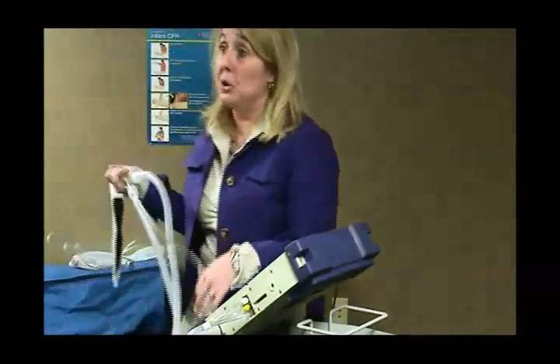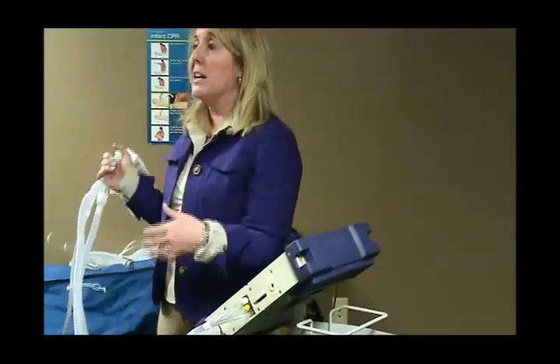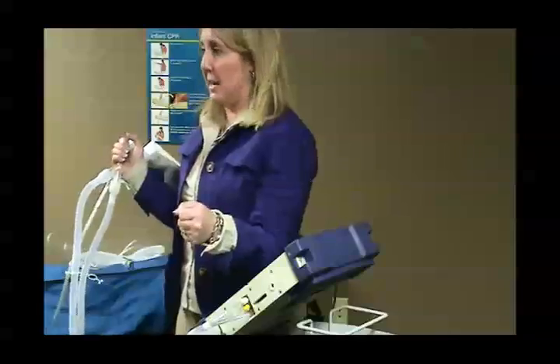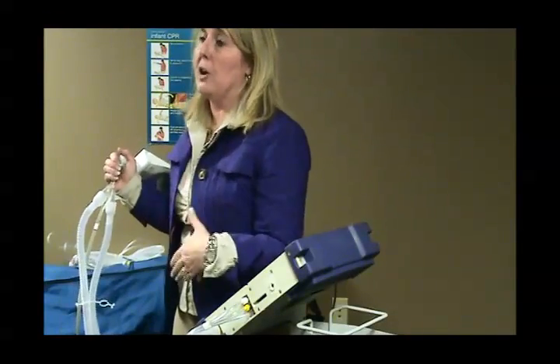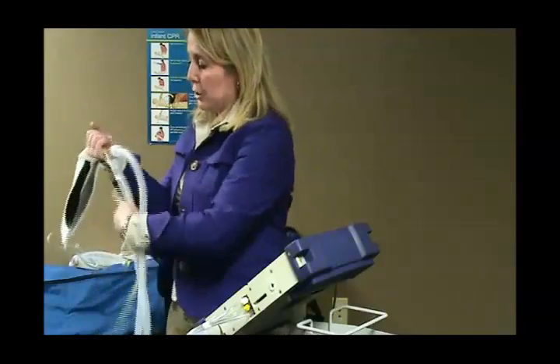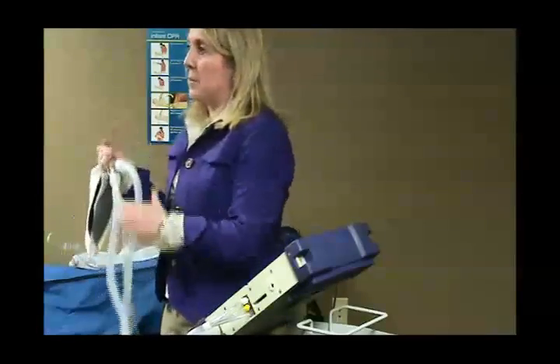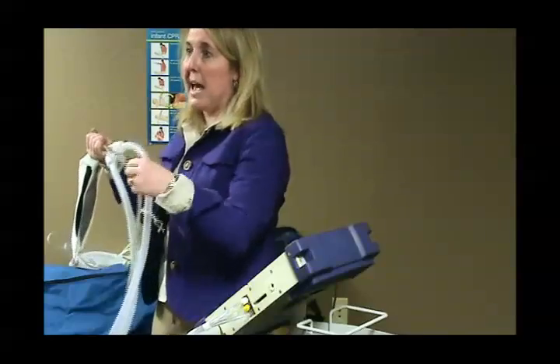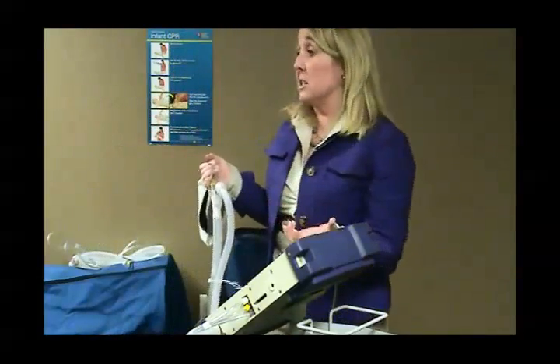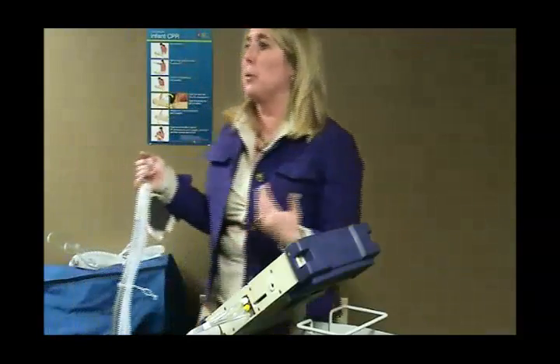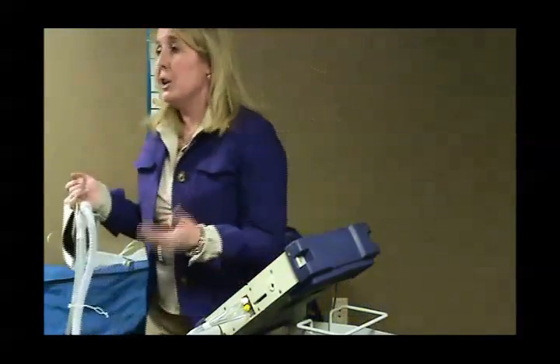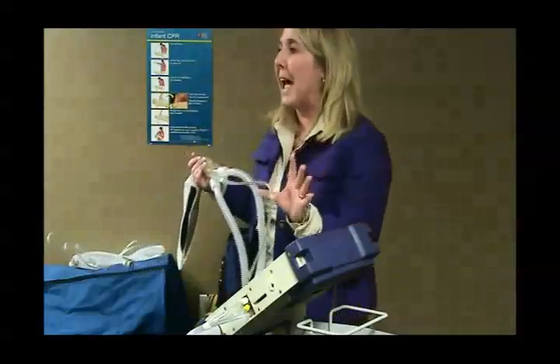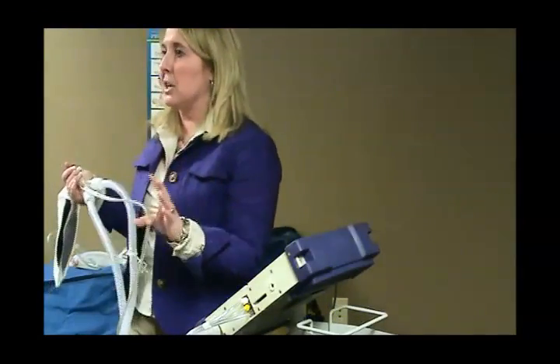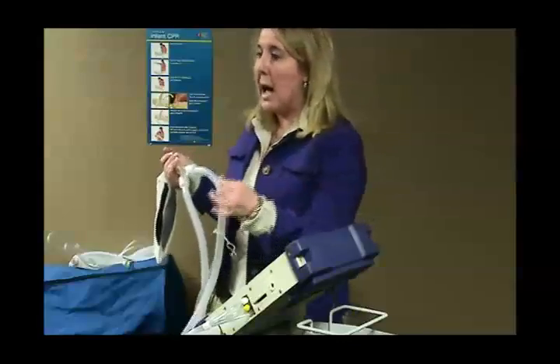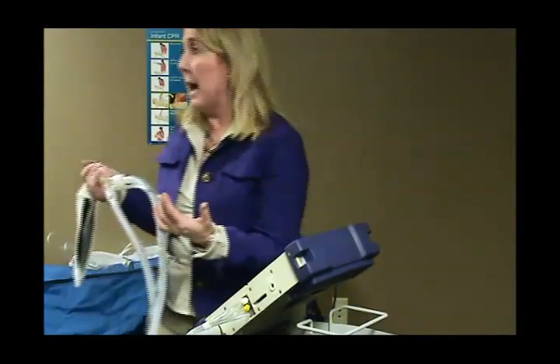So what I tell people to do is take that circuit off, put another circuit on. Once you get the patient all settled, everything's happy, take that circuit and hang it over the shower rod. Let it dry out. You can reuse that circuit for up to 30 days. So when circuits are changed, you should always have a little piece of tape tab on them that says when you changed the circuit, even if the equipment company people, the RTs, come out and change your circuits for you. If you have to change a circuit, you should tag it with the date and time, just like you do your saline when you open it and all that kind of stuff. That way you'll know if a circuit is still good or not.